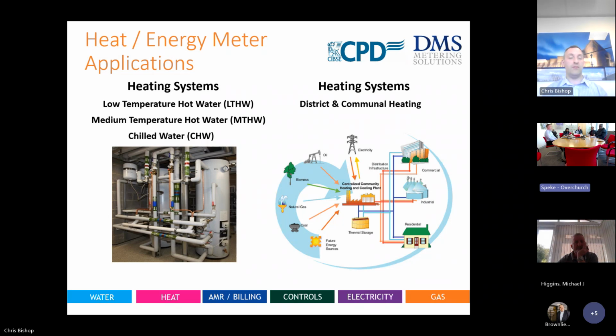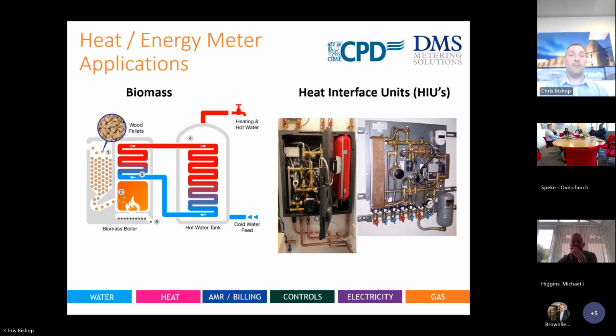And then chilled water as well, in individual locations, but getting more common now with the UK climate and some design factors that are happening in certain buildings. And then district heating and communal heating systems as well. You will generally see heat meters designed, specified and installed in those applications. Biomass, as I stepped onto earlier on, the Renewable Heat Incentive, is a requirement to have heat meters installed. Like I say, the scheme is defunct, but there's still demand for it moving forward for the next 10 years.